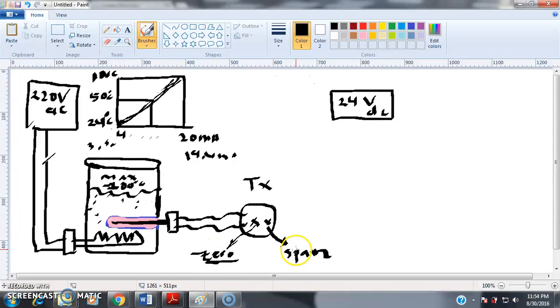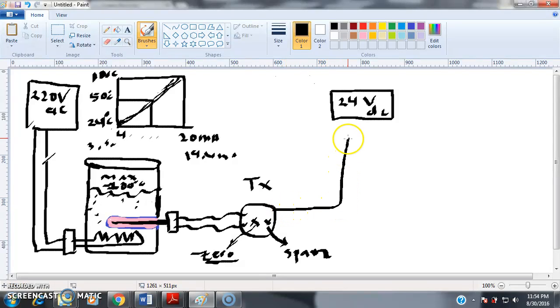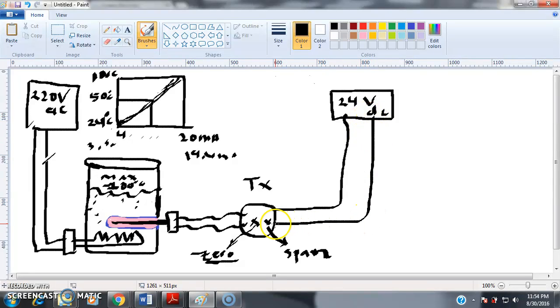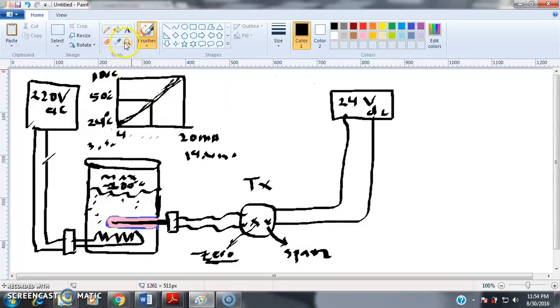The output of the transmitter goes to your 24-volt power supply — this is how you power the instrument. The output will be 4 to 20 milliamps. To read that signal output, you need to break one of the lines in the circuit and connect your multimeter there, in series with the loop.